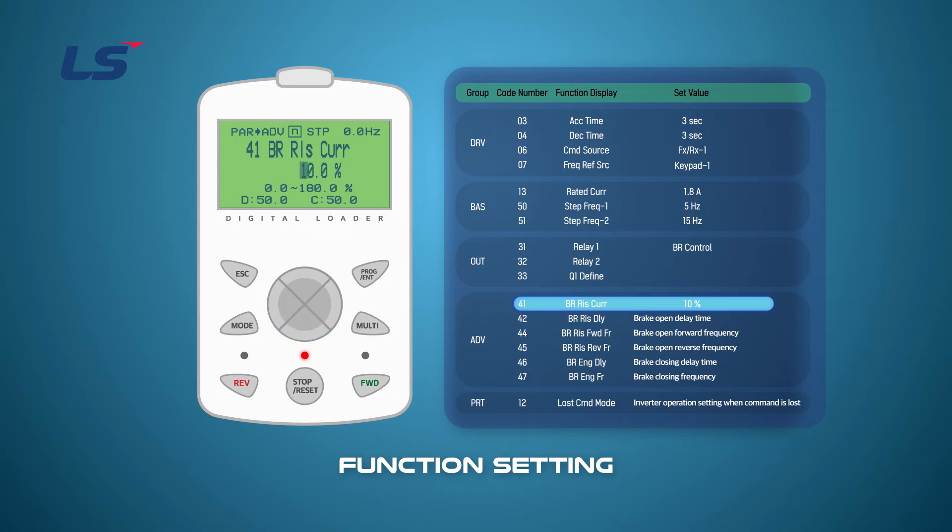The open current of BR control will be set to 10% of the motor rating. Since the rated current is 1.8 amps, it becomes an open current condition when it becomes 0.18 amps.